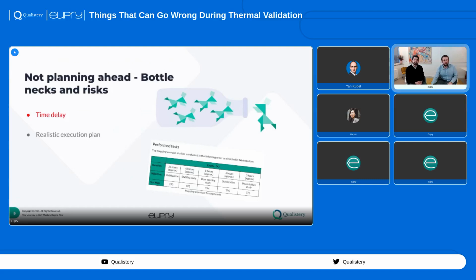Having a realistic execution plan is really important. We've included here a typical execution plan for an empty study, for example. Things like remembering that units need to stabilize after turning them on is a very common mistake—it can take up to 24 hours for a freezer to stabilize in temperature before you can start doing your studies. Stabilization after door openings is a common pitfall too: when stressing equipment by opening and closing doors to test the maximum operating range, it often takes at least 6 hours to stabilize again. If these things aren't planned for, they will cause time delays.